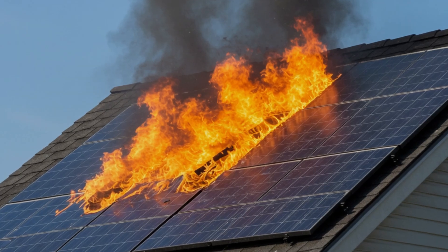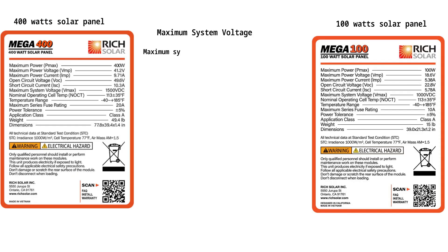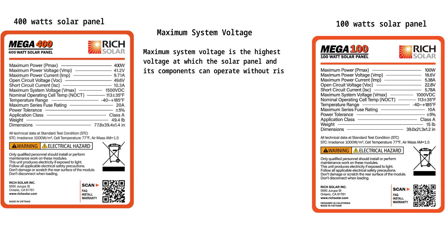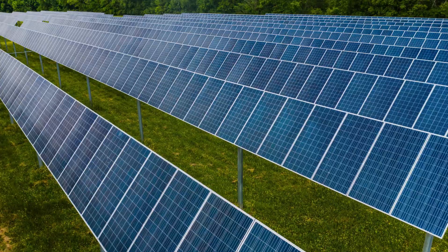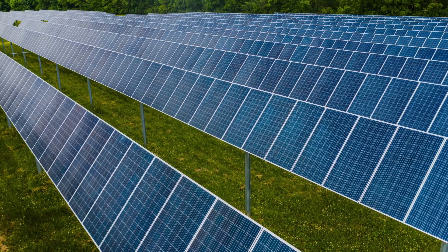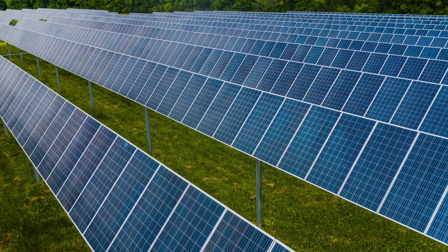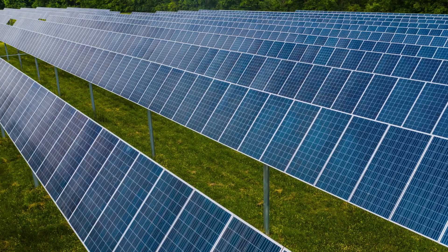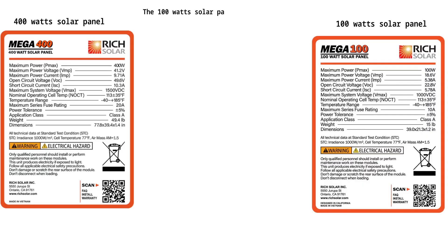6. Maximum system voltage is the highest voltage at which the solar panel and its components can operate without risk of damage, electrical failure, or safety hazards. Designing solar components within this range will help avoid damage. Its role in the solar setup design is that it shows the maximum number of panels that should be connected in a single series array. Looking at the 100-watt solar panel, it has a maximum system voltage of 1000 VDC.